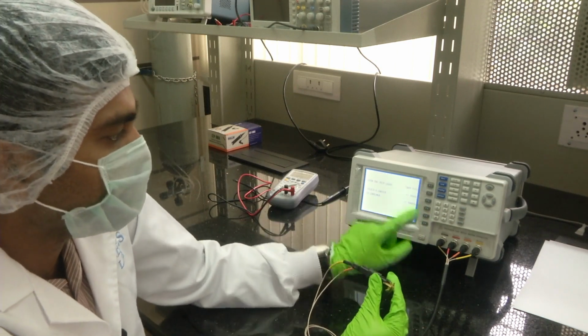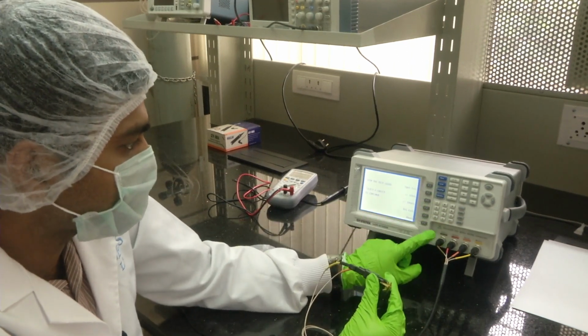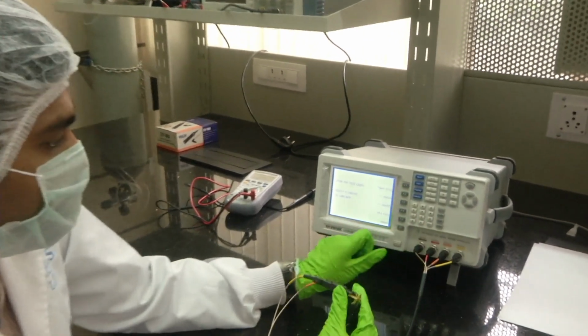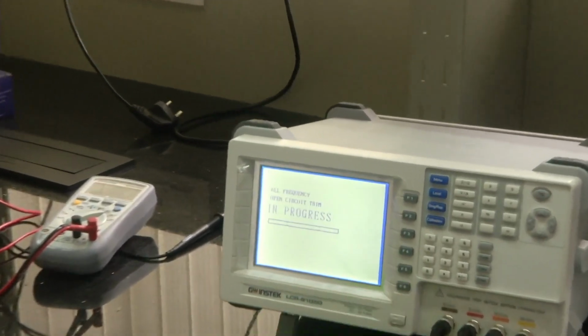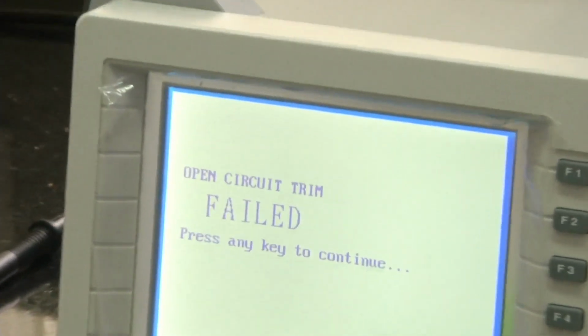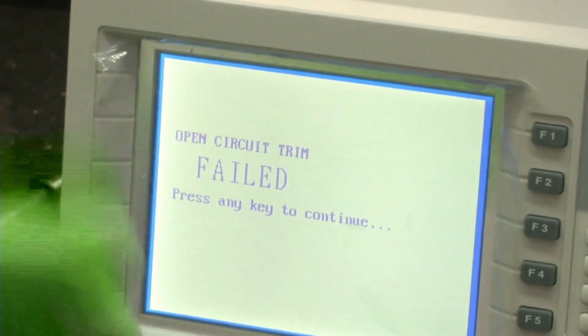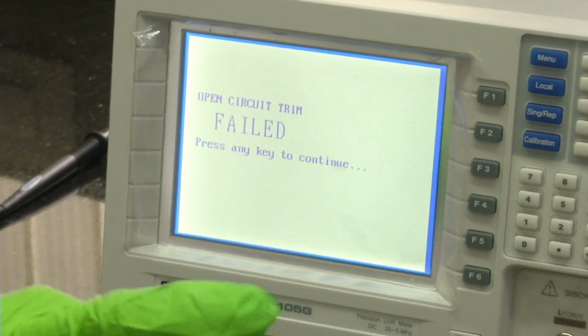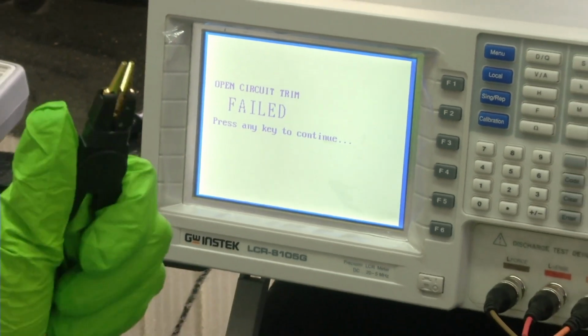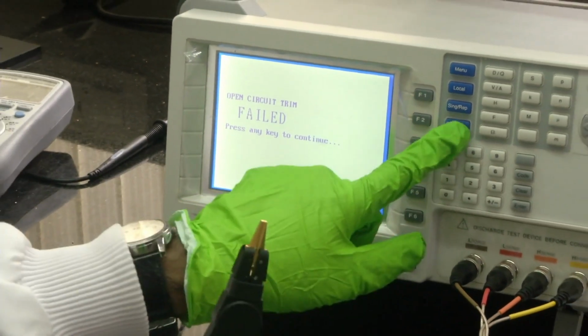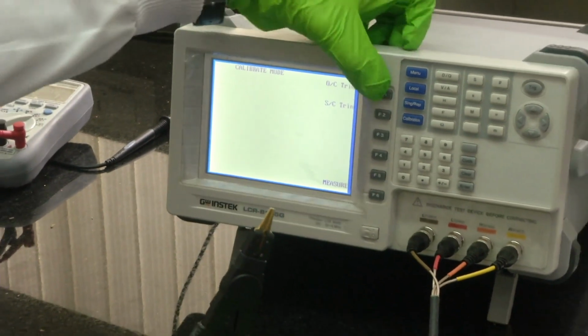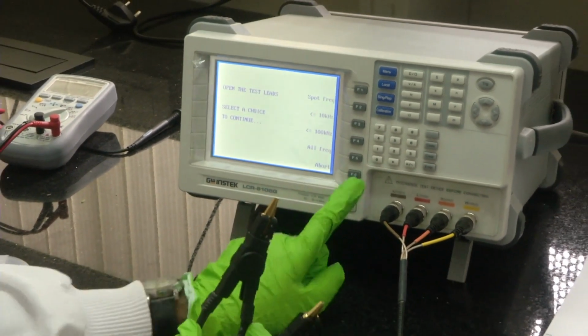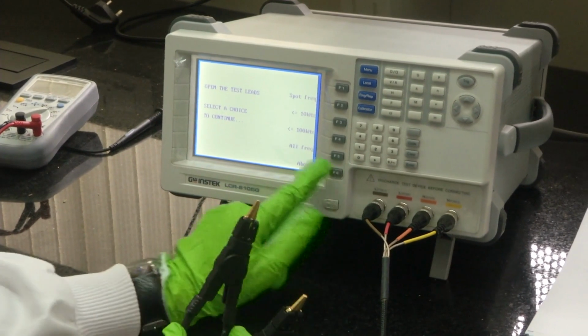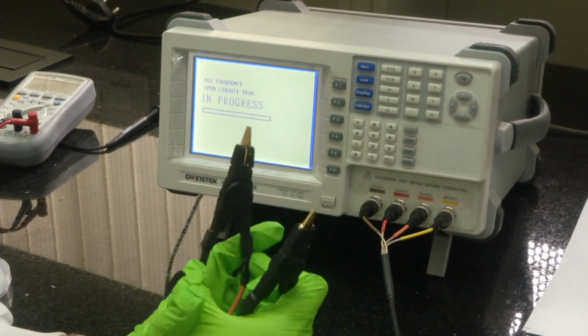So, again I go to calibration mode, I click open circuit calibration and I am calibrating for all frequencies. Now, this calibration process will fail. See, it has failed. This is because for open circuit calibration, you should not connect the probes and you should keep them like this. Now, let us repeat it once again. I go to calibration, I click open circuit trim. Trimming is same as calibration basically. All frequency, now it will calibrate.